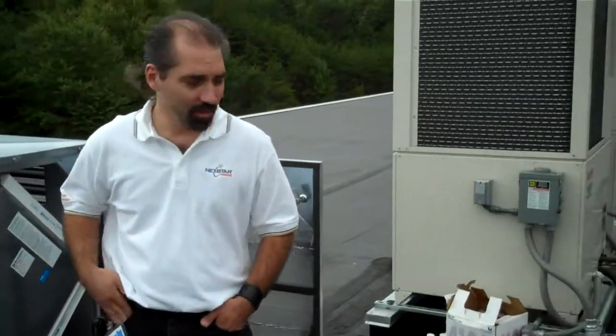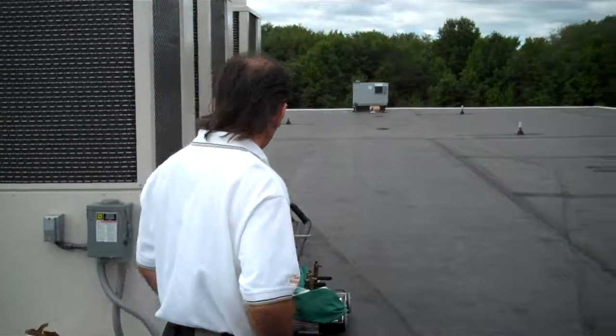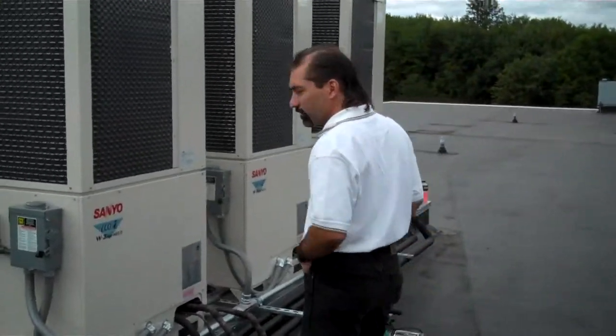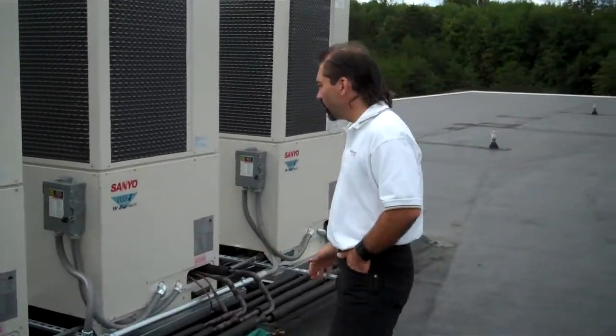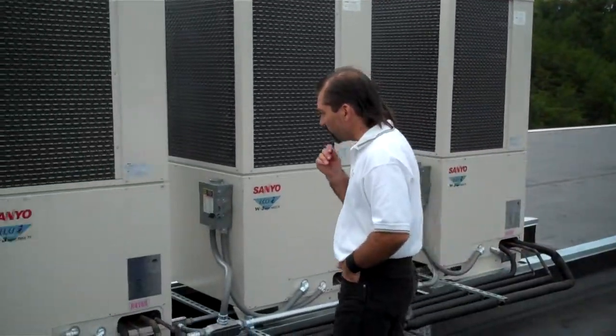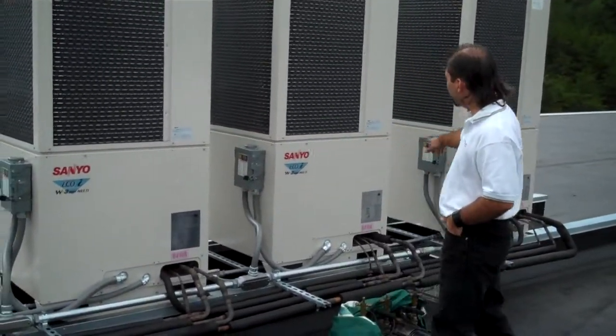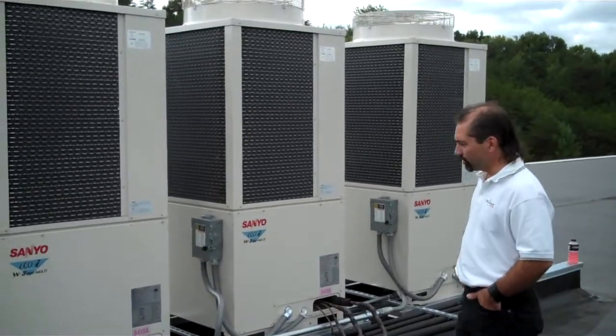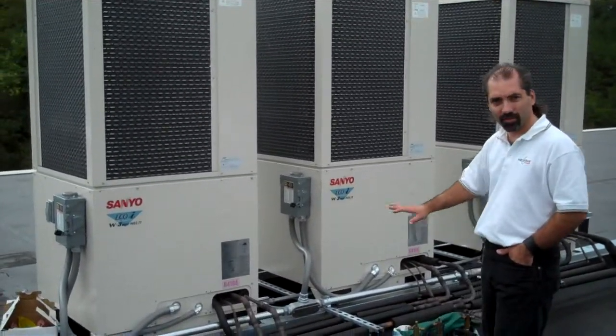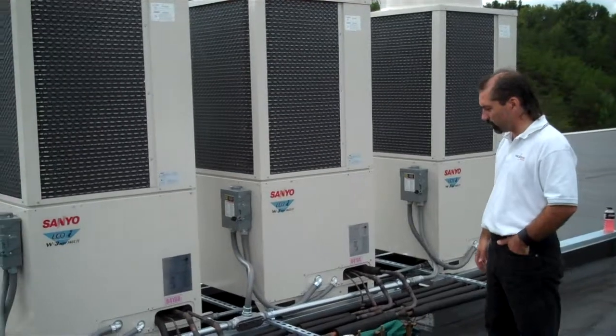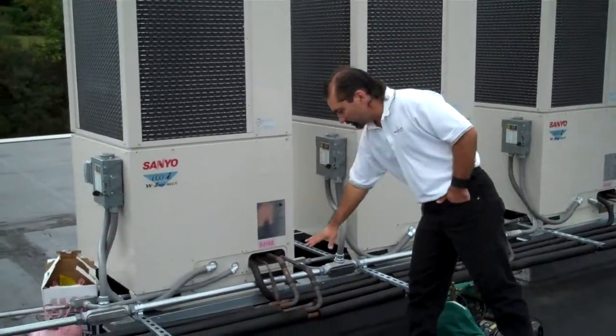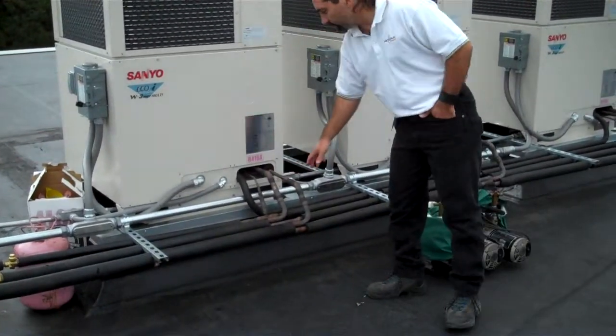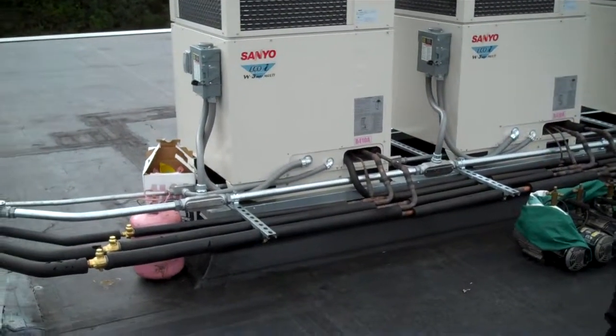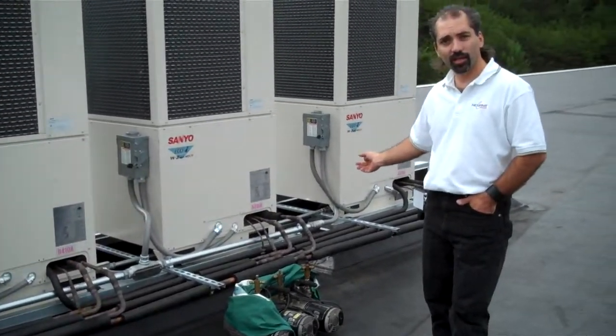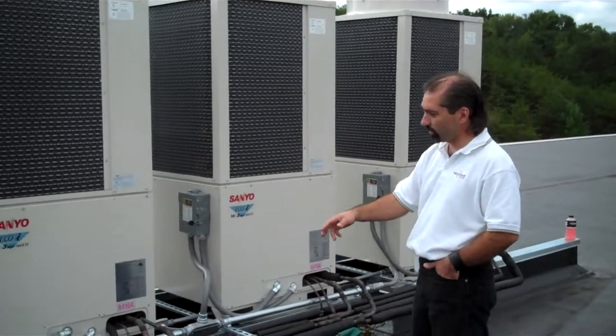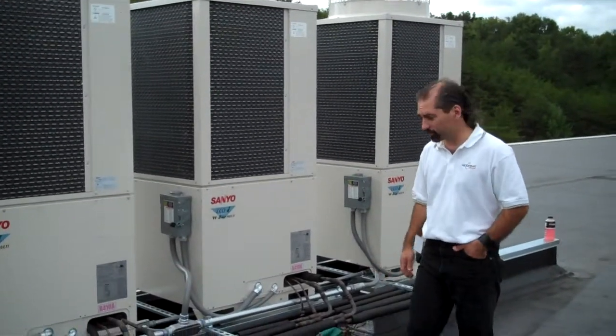Okay, and what are these large towers? These large towers are the second half of the ductless split systems that we've installed here, and I believe these are 2 7.5 tons, and this is a 9. So there's 15, about 24 ton of cooling. These 3 systems are solely for the first floor. And what you have here is your typical refrigerant piping with a suction and liquid line, and these lines are a little bit different because they actually have an oil equalizer line to make sure that we get oil return back to all the individual compressors.